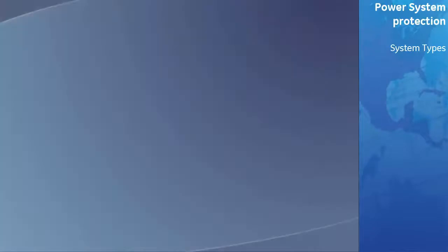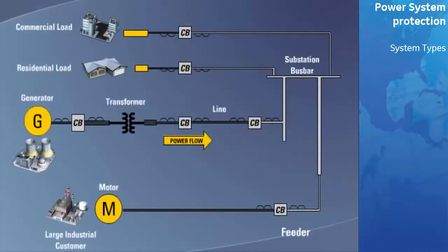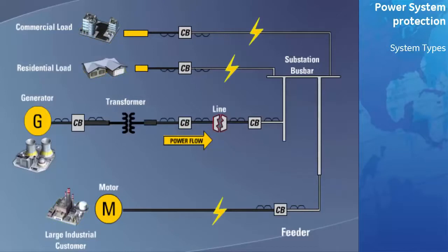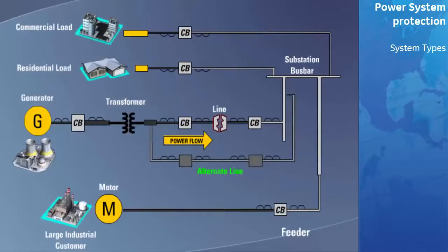The power system can be thought of as a chain, the links of which are the generators, the power transformers, the switchgear, the transmission lines, the distribution circuits, and the loads. The failure of any link destroys the capacity of the chain to do the work for which it was intended. One way in which the continuity of the chain can be preserved is to provide alternate links. The transmission lines, being exposed to the natural elements, are much more vulnerable to short circuit faults than the power transformers and switchgear. Hence, alternate transmission lines may be economically justified, whereas alternates for the power transformers and switchgear would not. The network of power systems now blanketing North America are often interconnected at various points to accomplish this.